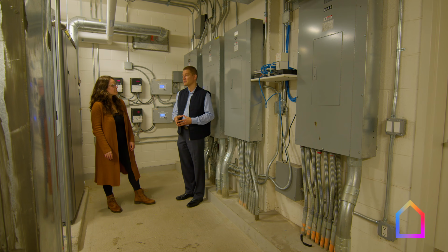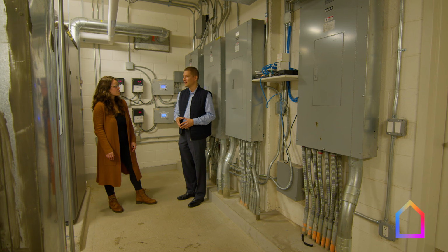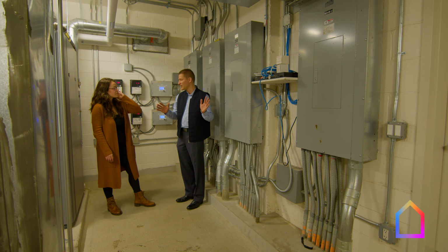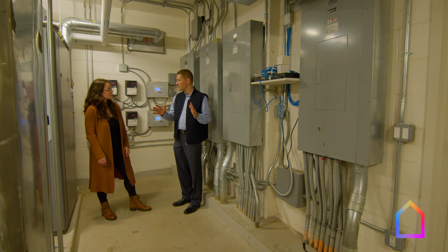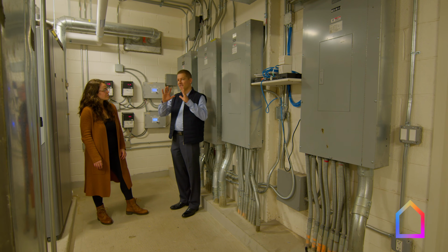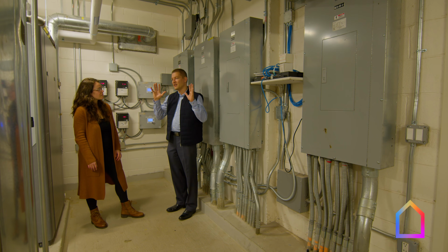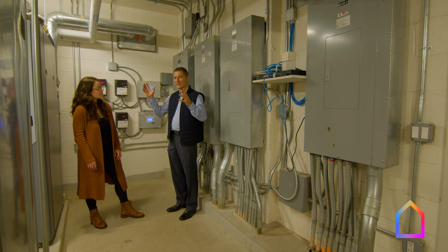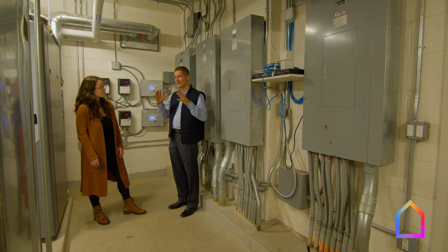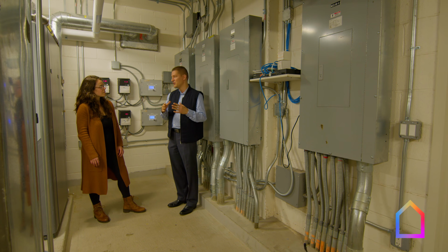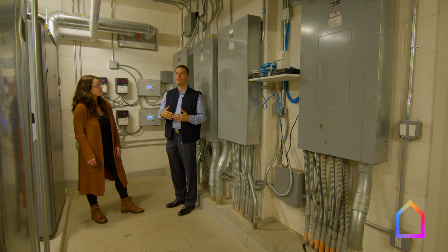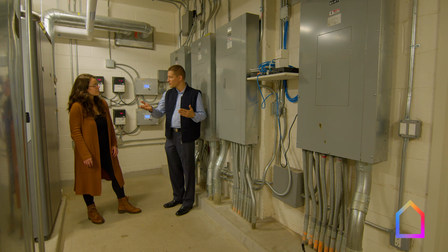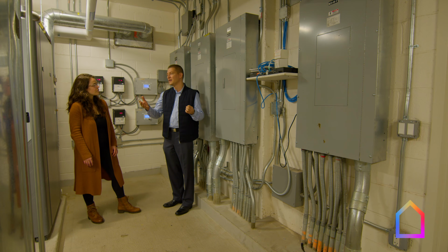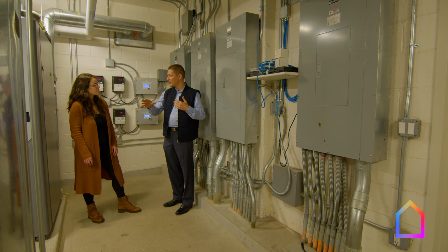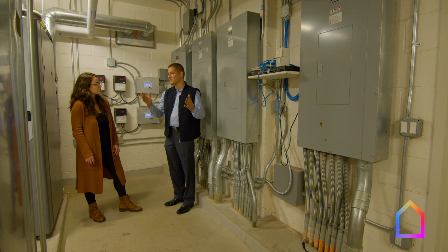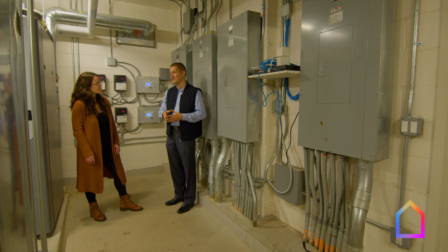So we put in a pretty intensive monitoring system so we can actually look at everything. It's not 100% finished yet, but outside of the VRF units in the apartments, we can see the set points on the thermostats, humidity levels in the apartments, humidity levels in the outgoing air streams at the ERVs, incoming and outgoing air temperature at the ERVs, and how fast the wheels rotate in the ERVs.